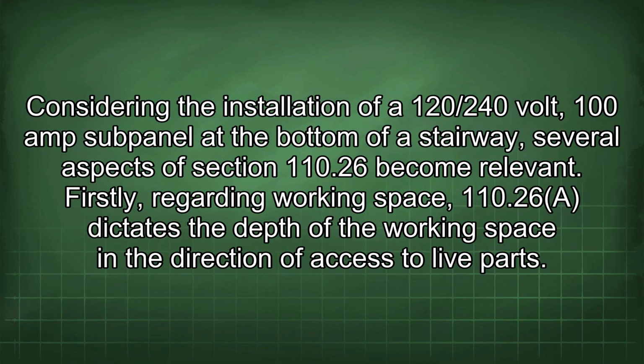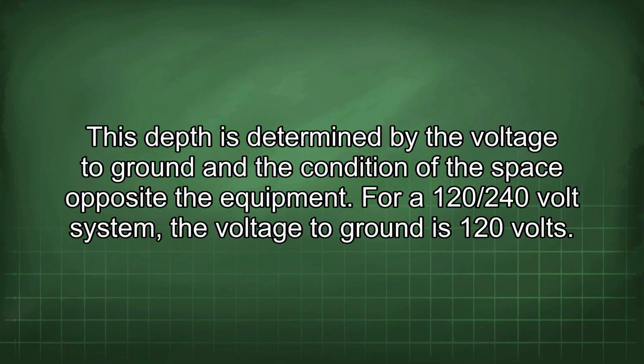Considering the installation of a 120/240 volt, 100 amp subpanel at the bottom of a stairway, several aspects of Section 110.26 become relevant. Firstly, regarding working space, 110.26 dictates the depth of the working space in the direction of access to live parts. This depth is determined by the voltage to ground and the condition of the space opposite the equipment. For a 120/240 volt system, the voltage to ground is 120 volts.